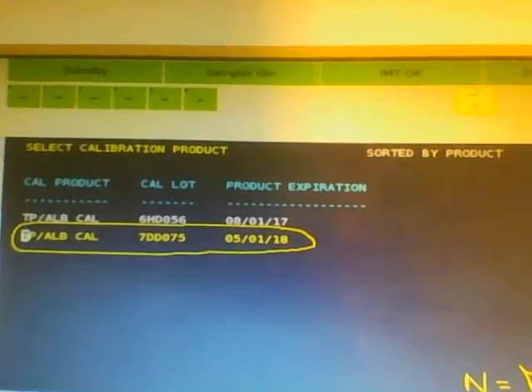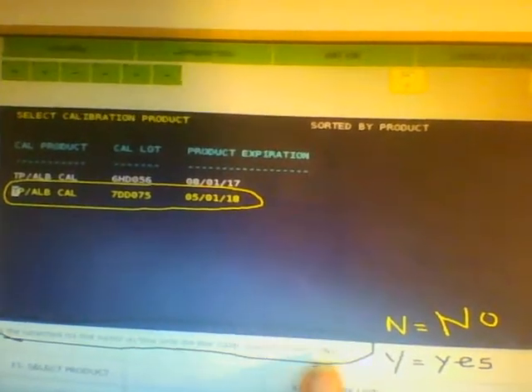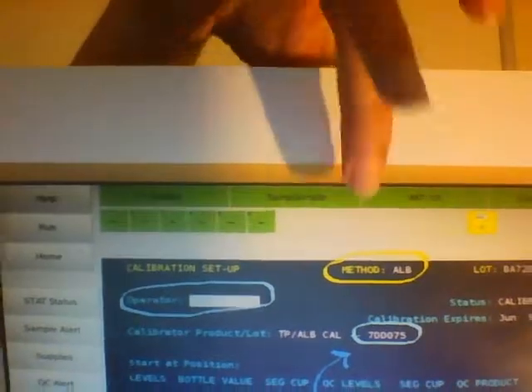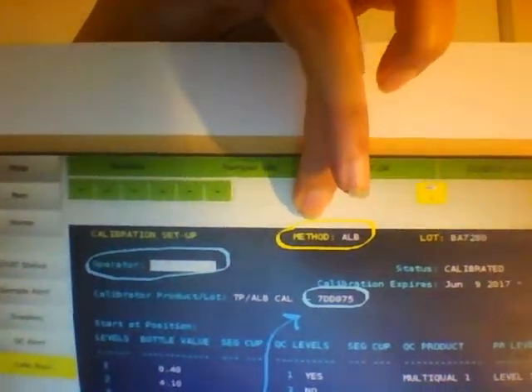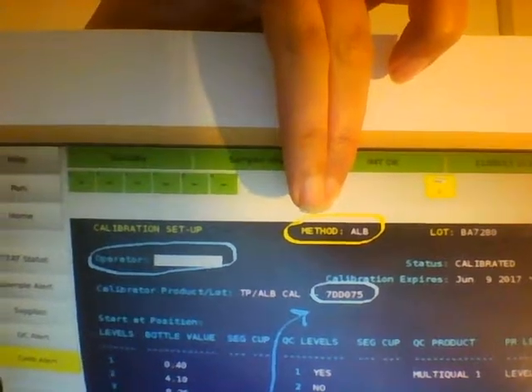And I put a yellow highlight so you could see. And then it's going to ask, is this what you really want? If that's the calibrator you want, go ahead and push yes. If not, push no. Once you push yes, you come up to your actual calibration screen. Your calibration screen is going to look like this, and your method is going to be whatever you chose. In our case, we chose albumin.